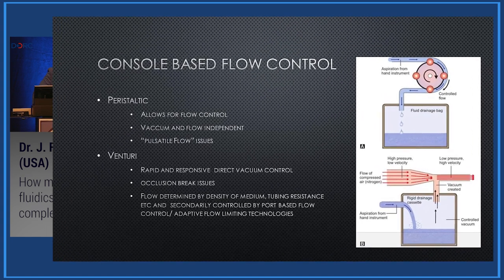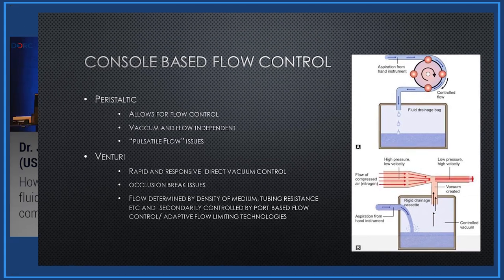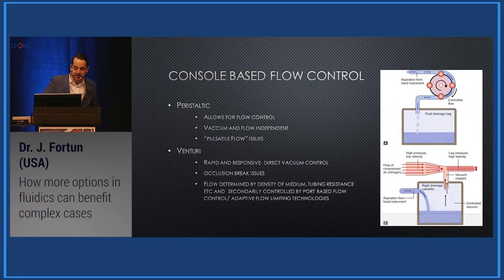Peristaltic machines, more familiar to European colleagues, allow for flow control where vacuum and flow are independent. However, there are issues with pulsatile flow in the posterior segment — we don't want pulsating retina or vitreous. Venturi pump consoles allow for rapid, responsive vacuum control, which increases efficiency and allows quick tissue manipulation, but there are occlusion break issues. Neither system in and of itself is an ideal platform for console-based flow control.